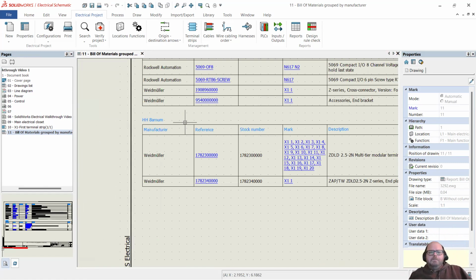Especially the way I like to look at these drawings and the documentation, and the reason that I say over document, right? If there's a description field, if there's something that lets you be clear, use it. It isn't necessarily because of you. If you're designing these, odds are strong you know what you did. Even if it's 10 years down the road, you know your style intuitively, and you know how to find things. If it's 10 years down the road, there's a maintenance guy who just got out of school, just started on your floor, and he has to fix this machine. He may not have any idea where you buy one of these terminal blocks.